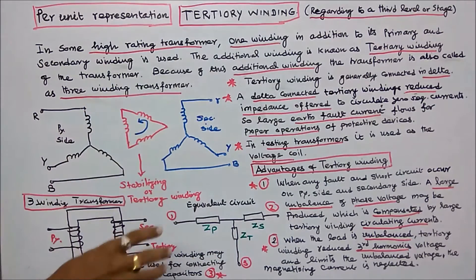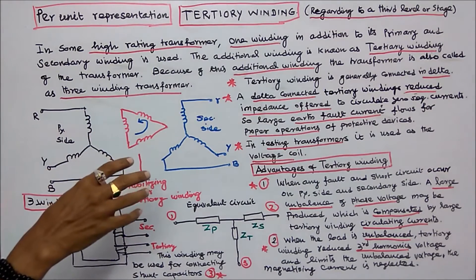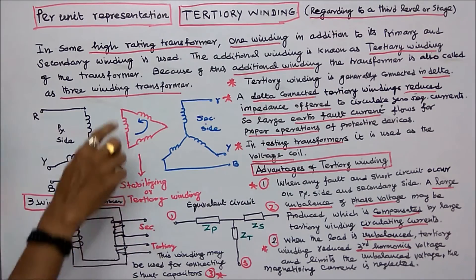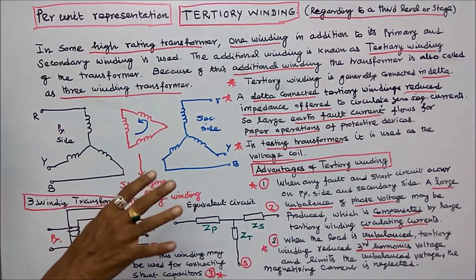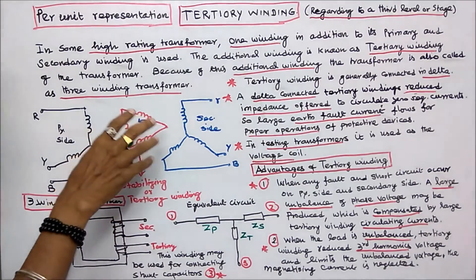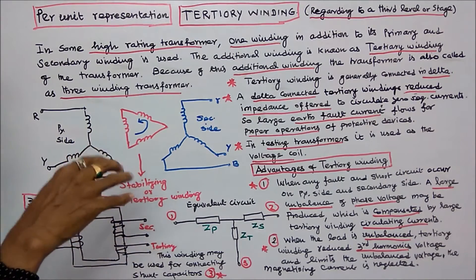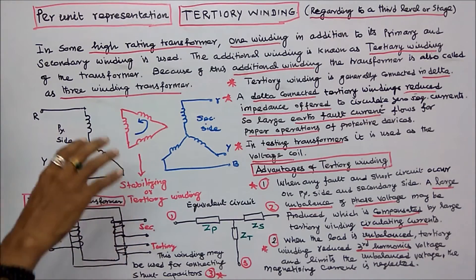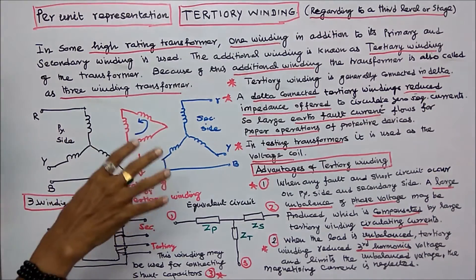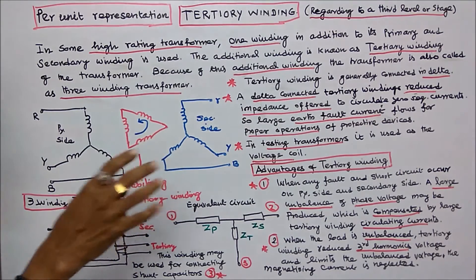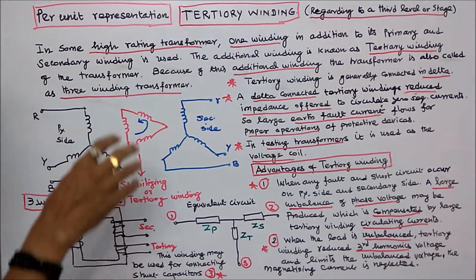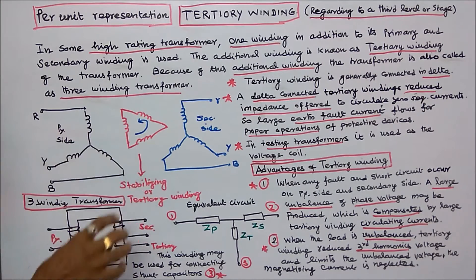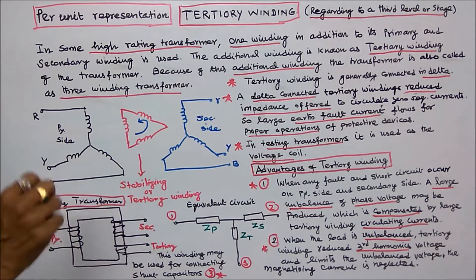Because of this additional winding, the transformer is also called a three winding transformer. The tertiary winding is generally connected in delta. A delta-connected tertiary winding reduces the impedance offered to circulating zero sequence currents, so large earth fault current flows for proper operation of protective devices. In testing transformers it is used as the voltage coil.